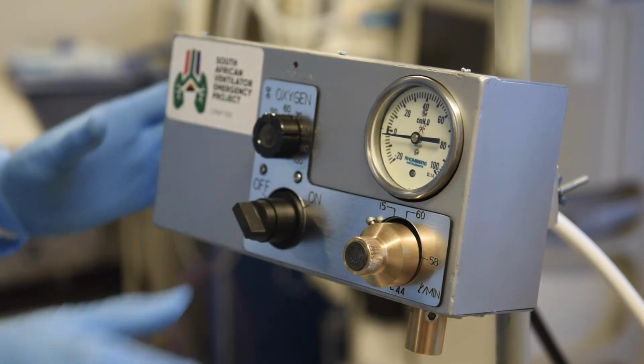Now that your CPAP 100 is properly set up and delivering oxygen under pressure to your patient, you must continue to monitor them 24 hours a day, because there are no alarms on the CPAP 100 which will warn you if your patient deteriorates. It is your responsibility to make sure that they are getting enough oxygen by means of a pulse oximeter and that they are not getting into respiratory distress.